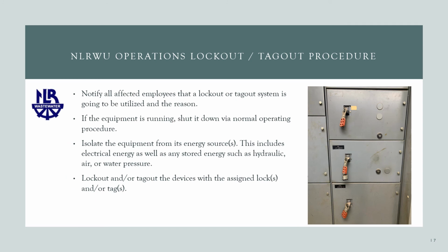As to the actual procedure, the sequence should look like this. First, notify all affected employees that a lockout or tagout system is going to be utilized and the reason. If the equipment's running, shut it down via the normal operating procedures. Isolate the equipment from its energy sources. This includes electrical energy as well as any stored energy such as hydraulic, air, or water pressure. Lock out, tag out the devices with the assigned locks and/or tags.